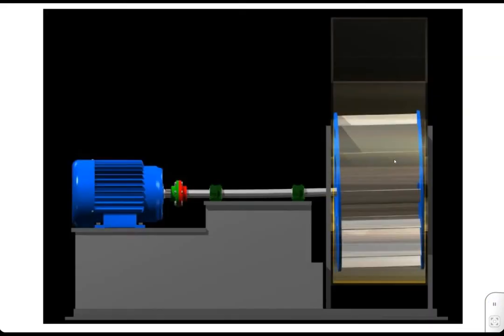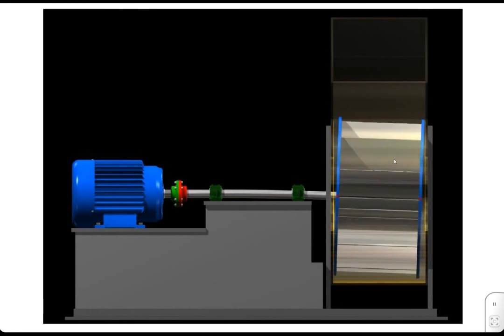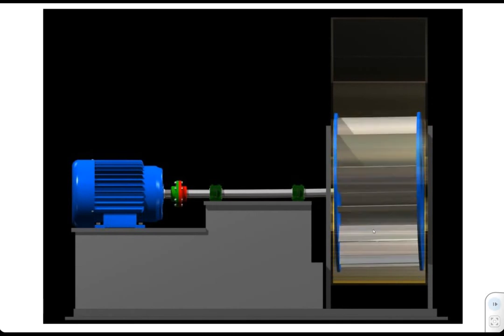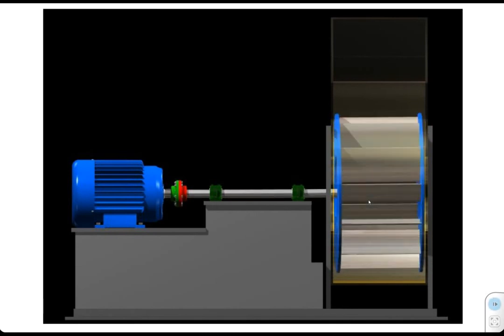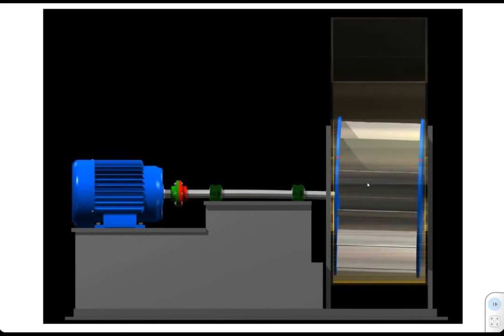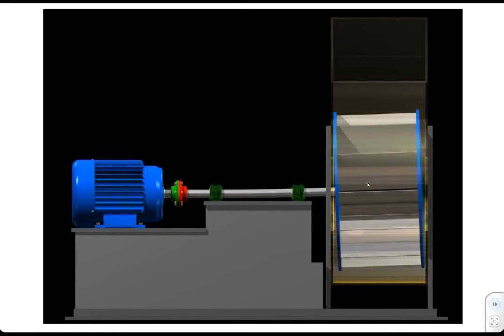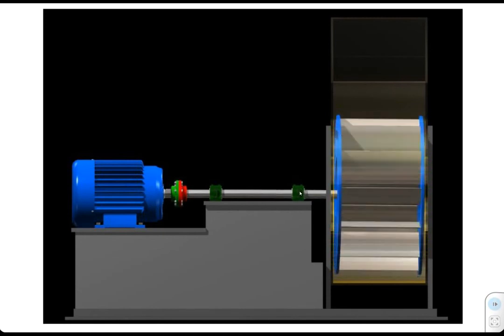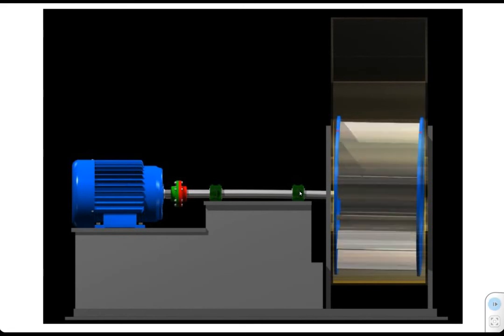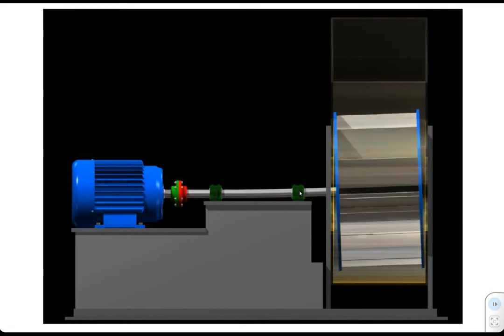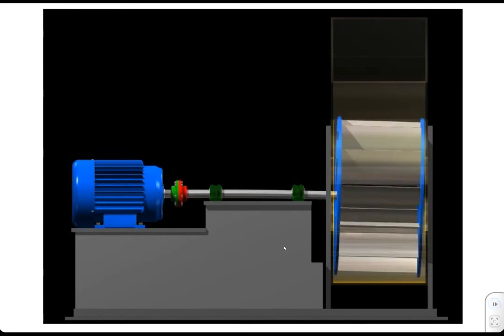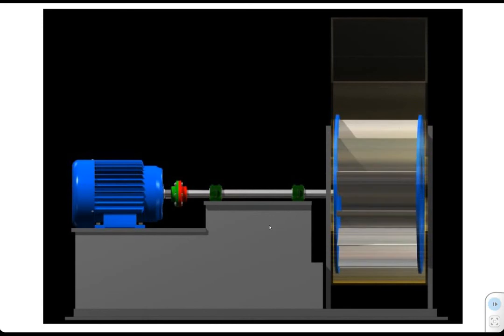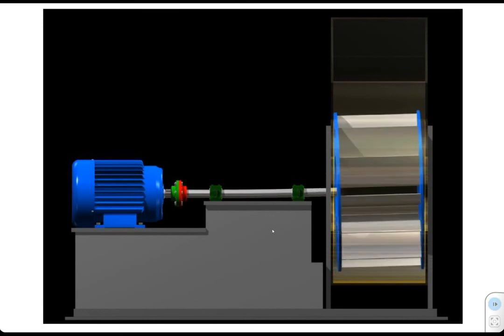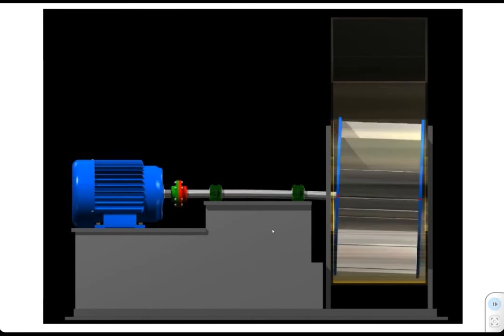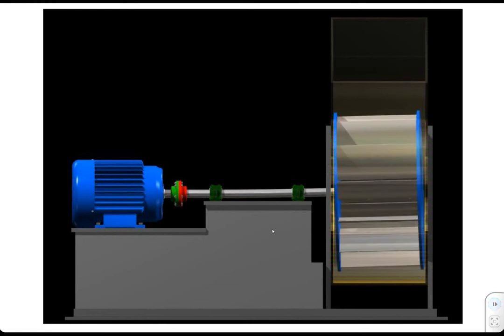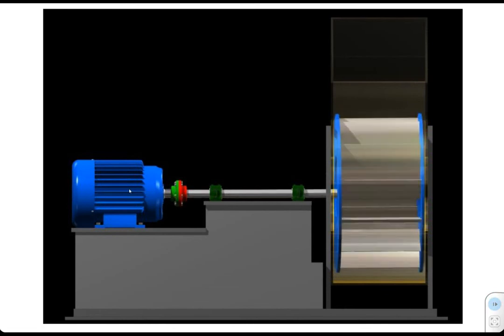If we don't keep the machine's precision balanced, then as the shaft turns, it rocks when it's overhung like this. It tries to move up and down because of the centrifugal forces. And these bearings just don't like that. The extra load on the bearings drastically reduces their life. The whole structure doesn't like it. We can have cracking and failure. The vibration can get into other machines. The vibration can excite things called resonances. It can affect the coupling and the motor itself.